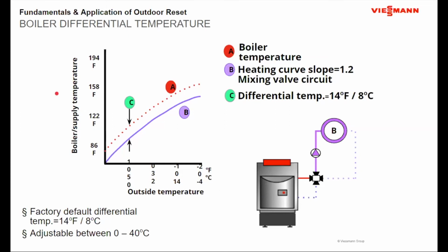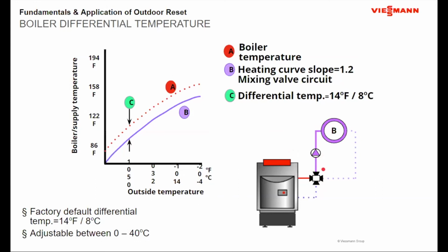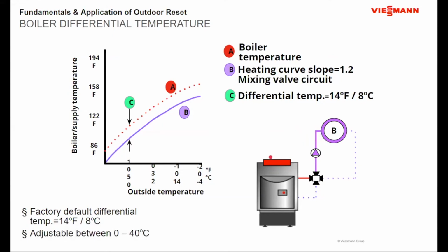Okay. Now, a couple other things to be concerned with. You start to look at heating curves and how things are performing, and a lot of projects for multiple water temperatures will offer mixing valves. Here happens to show a non-condensing boiler with a 4-way. It could also be a condensing boiler with a 3-way as well. And why this is important is if I have the boiler set up on its own heating curve to provide a certain water temperature prior to the mixing valve, the methodology of the boiler control is not only to look at the water temperature for its programmed heating curve, it also looks at the requirements of any mixing device or any other device that's associated with it.